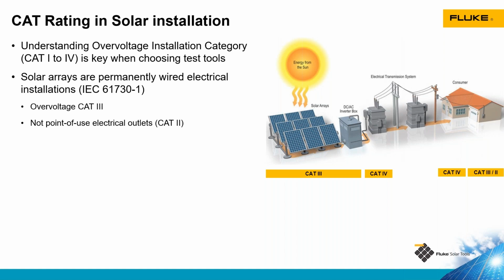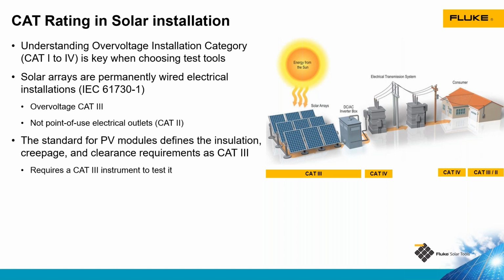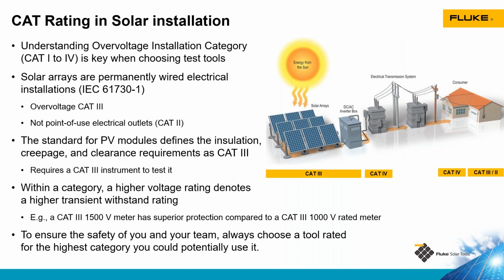According to this IEC standard, solar arrays were considered a Category 3 environment. We also do a lot of testing in Category 4 environments, which would be closer to the point of interconnection of our inverters, or if you're on a utility scale system, between the inverter and the medium voltage transformer.